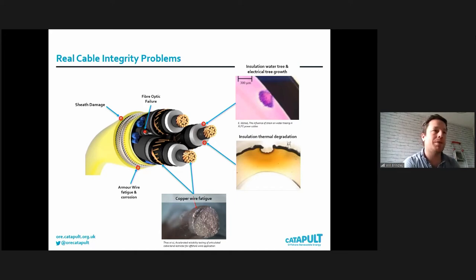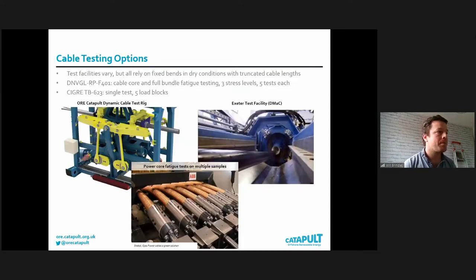And the other area of research we're looking at is also insulation, water tree growth and electrical tree growth. And it's not fully understood how that interacts with the mechanical strain that the insulation is going to see in a dynamic cable. So to make sure that our cables are good for this kind of service over the long term, you need to test the cables.